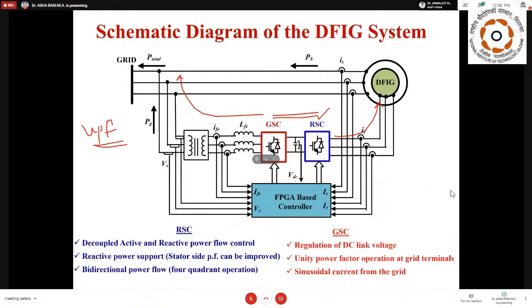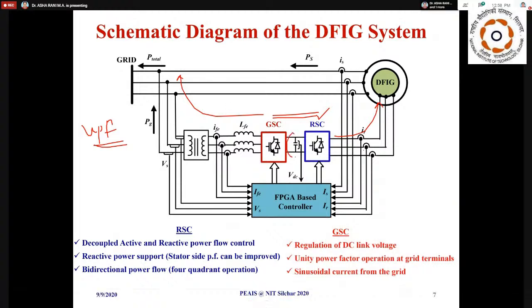And then we can see there is a grid side converter. The basic role of the grid side converter is to maintain this DC link voltage constant, because whenever we are consuming something and trying to inject reactive power here, there is a tendency for this to fall. So GSC will take care of that and make this constant. Another thing is, when there is any grid distortion or some issues happening in the DFIG, sometimes it needs additional reactive power, especially during unbalance. At that time, the needed reactive power can be pumped like this also. So again, no need to take from the grid. That possibility is also there.